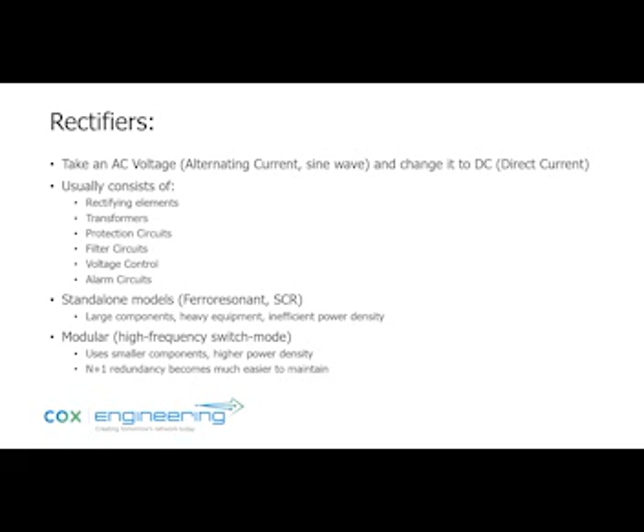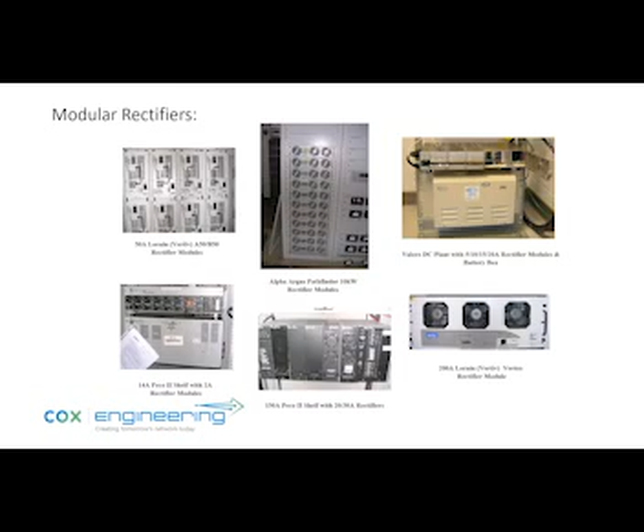Now, in the past 25 years, or 30 years really, modular, high frequency switch mode rectifiers have been used. They use smaller components. There's a higher power density. It's easier to maintain N+1 redundancy. So what happens within those is that it boosts up the frequency so you can use smaller components, and as you probably have seen inside of your head ends, the rectifier modules are becoming smaller and smaller. Now here are some pictures of a few older ones. I could have updated them because they're even smaller these days. As you can see, they're generally plug and play, and you can have a small customer premise size at the top right, the larger head end size in the center, the upper center alpha plant, and everywhere in between.